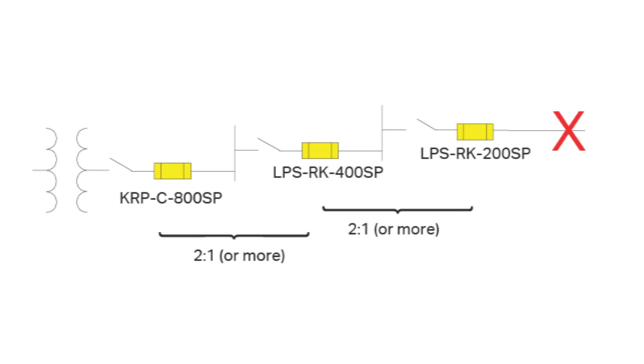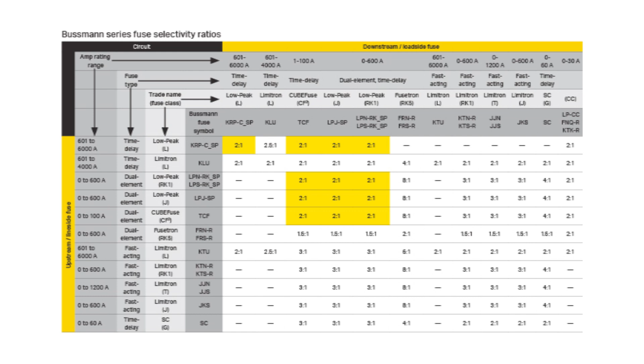Here we can see the minimum amp rating ratios for Eaton's Bussmann series Low-Peak fuses required to provide selective coordination between upstream and downstream fuses. It's a simple matter to selectively coordinate a system using published fuse amp rating ratio tables and maintaining the minimum ratio between an upstream and downstream fuse. This will ensure selective coordination is achieved for all fault currents up to the fuse's interrupting rating. The fuse selectivity ratios can be found in the selectivity ratio table in the Bussmann Series Fuseology Technical Guide or the Bussmann Series Electrical Protection Handbook, SPD.